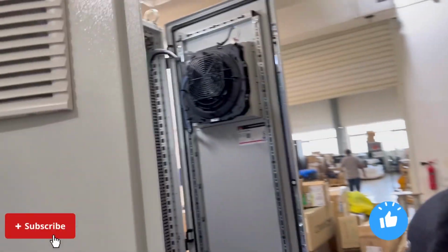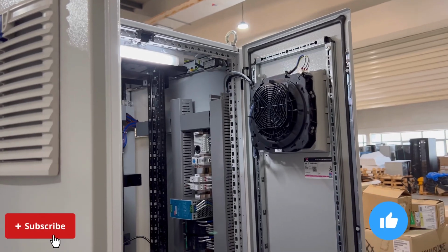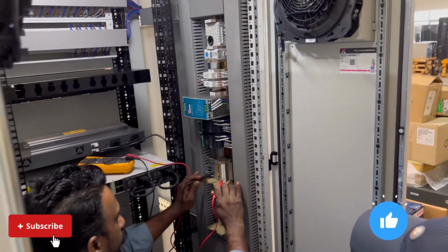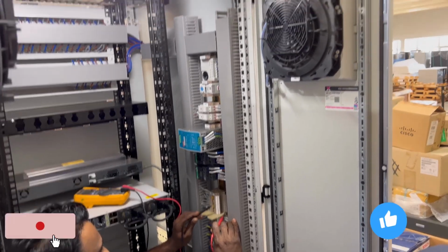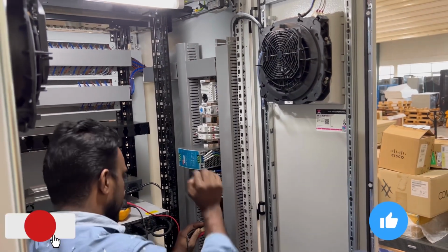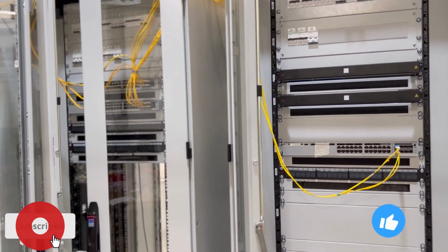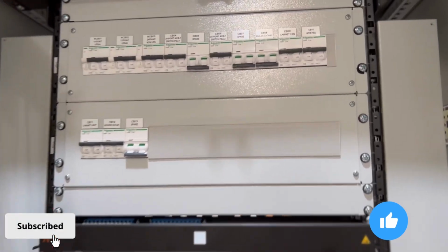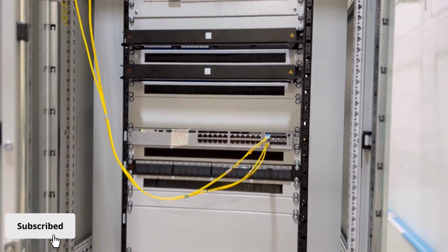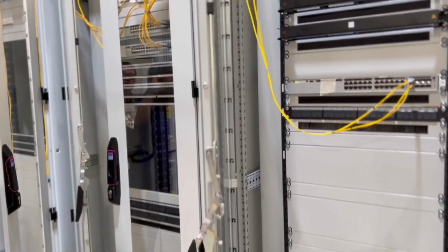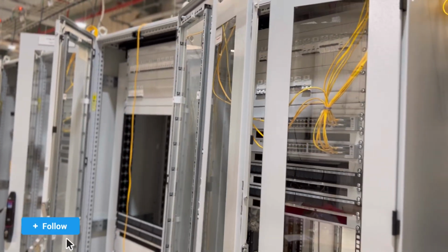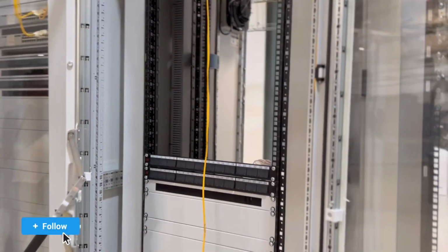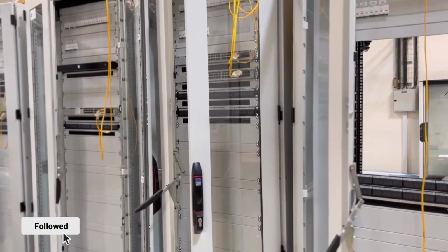One thing also, guys, you need to check the calibrations of their equipment and devices. If they're using a laptop, check the laptop, and check their calibrator, check the test equipment. You need to check all of that, so that it will be recorded during your release note when you're releasing the materials. So that's part of your punch list and part of your report as well. You need to consider all of those materials to be carried out during your inspections and testing. Okay, so that's the most important thing.